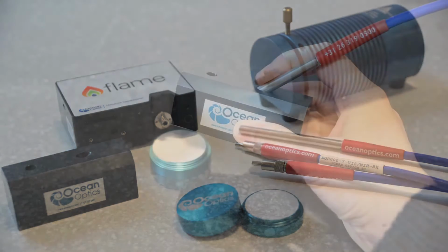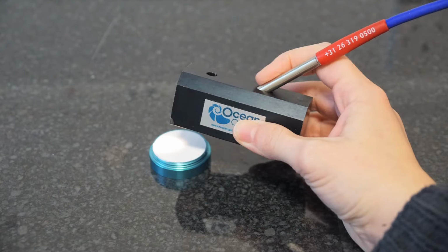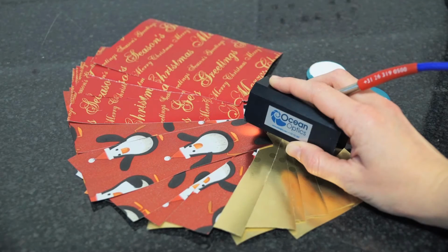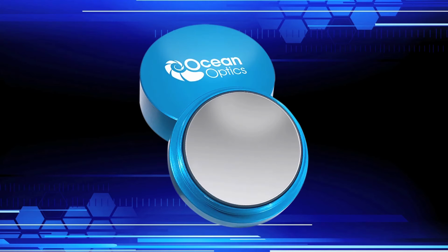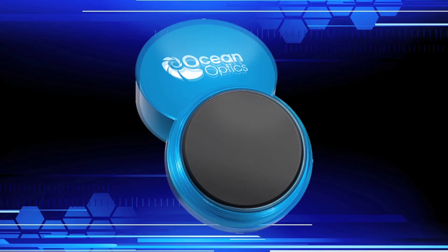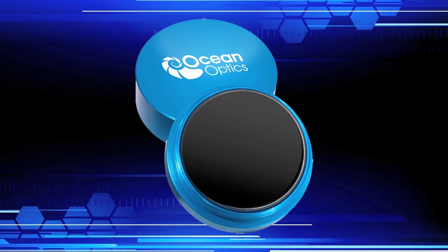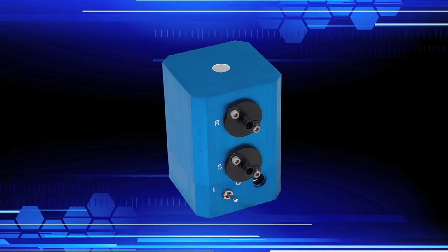You should always try to ensure your reference measurement uses a reflection standard that is as close to your sample as possible. If measuring off a highly reflective specular surface, use a reflection standard such as STAN SSH. Similarly, for low reflectivity, use STAN SSL. For some applications, it may be helpful to use an integrating sphere such as the ISP REF.